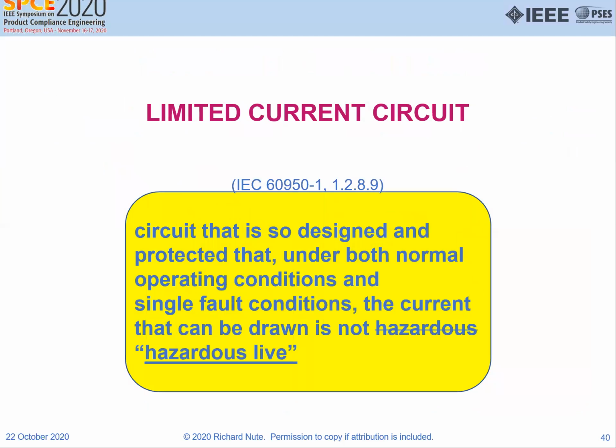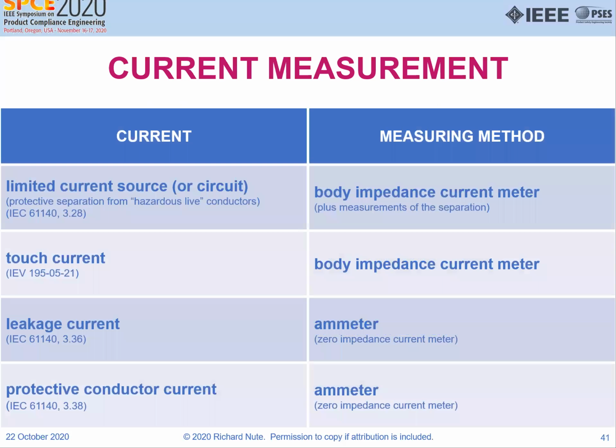So a limited current circuit is a circuit that is so designed and protected that in both normal operating conditions and in single fault conditions, the current that can be drawn is not hazardous live. That's from 950. I changed this; it said hazardous, and I changed it to say hazardous live. So the current of a limited current source is measured with a body impedance current meter.